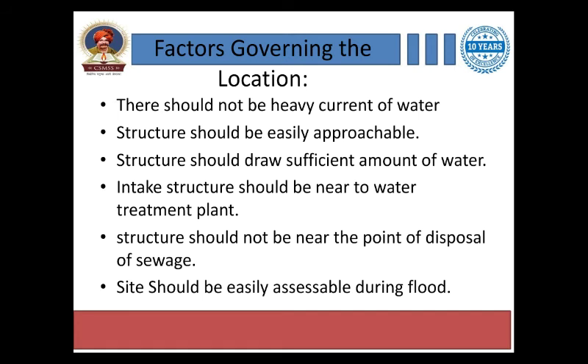What are the governing factors that affect or decide the location of intake structures? Following factors apply: There should not be heavy current of water — if there is heavy current, we cannot provide an intake structure at that place. The structure should be easily approachable to the staff of the irrigation system or water supply system. The structure should draw a sufficient amount of water. The intake structure should be near to the water treatment plant. The structure should not be near the point of disposal of sewage, so that it will not spoil or disrupt the quality of the water drawn. And the site should be easily accessible during flood time also — if it gets flooded, we should still be able to approach the site.